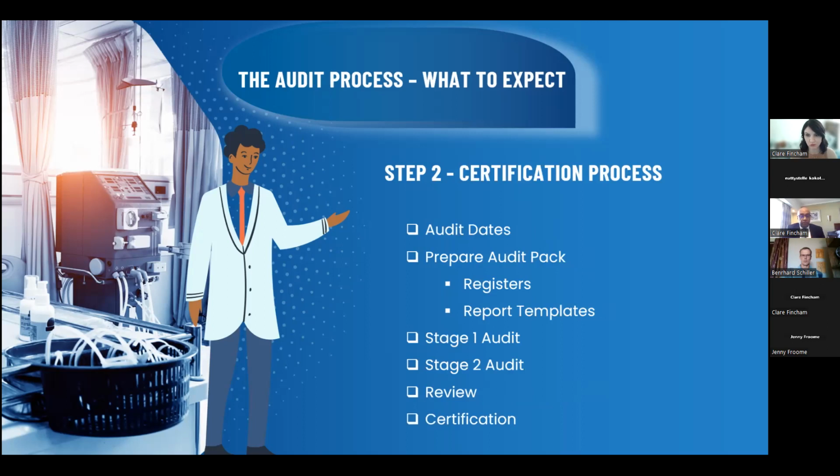One would need to undergo an audit that would look at to what extent your policies, processes, and systems in place meet the requirements of the standard. So typically there is a stage 1 audit, and stage 1 looks at whether there are provisions in terms of processes, facility, technology, and checks and balances to ensure that your medical device processes are well managed. The stage 2 audit is really where everything gets looked at in a fair amount of detail.